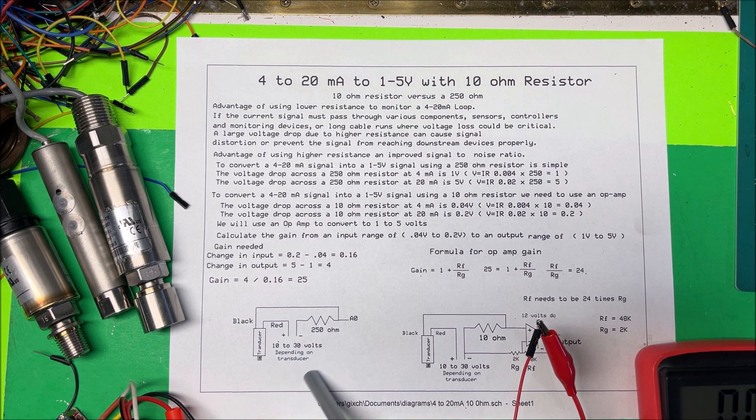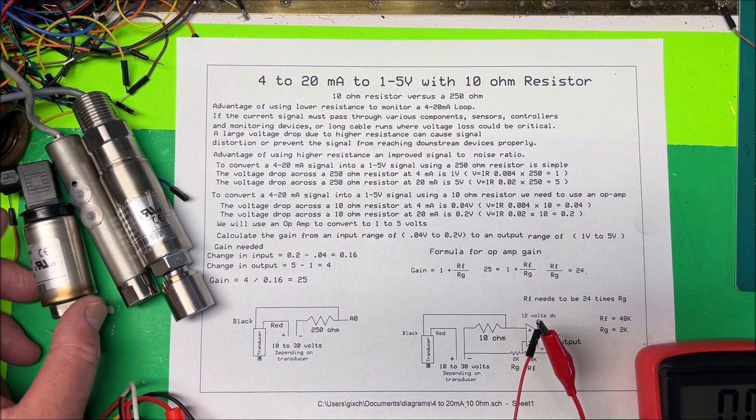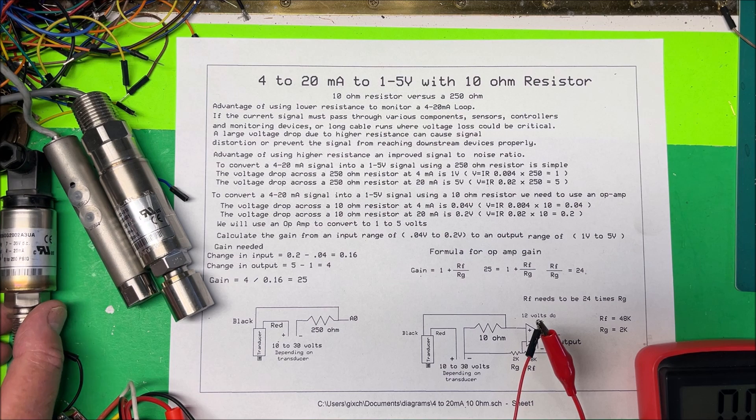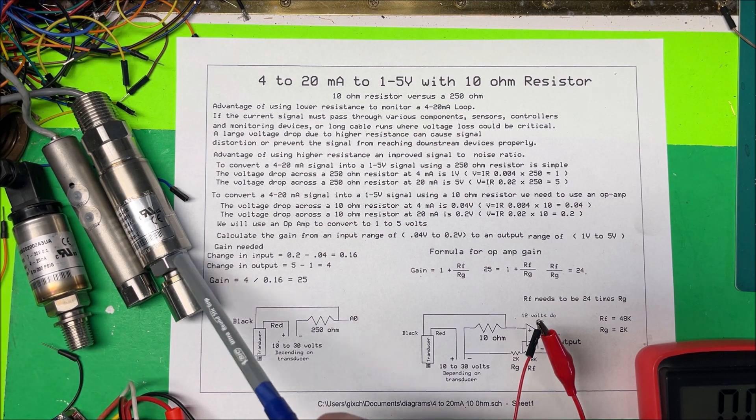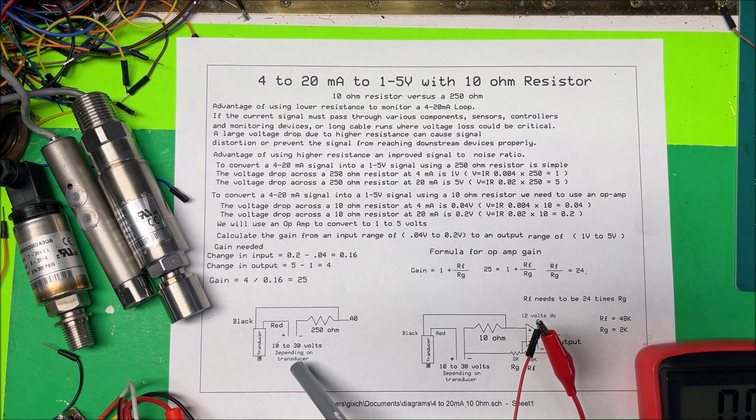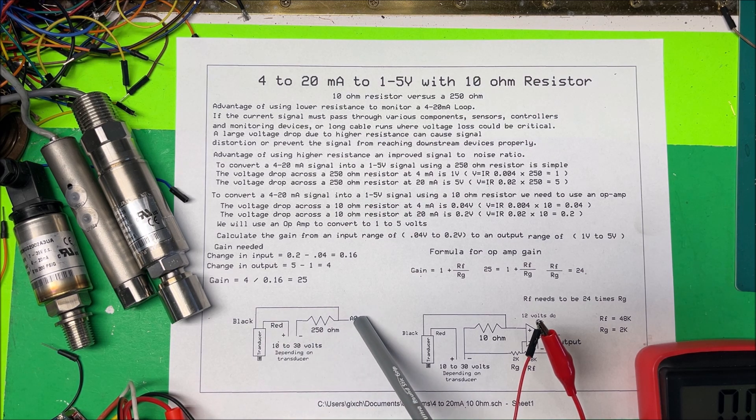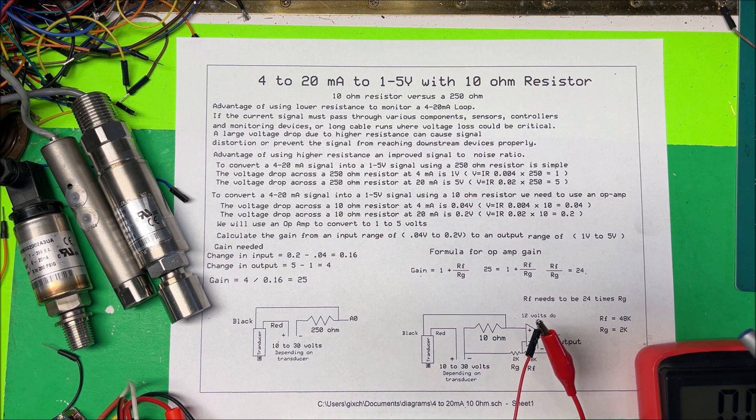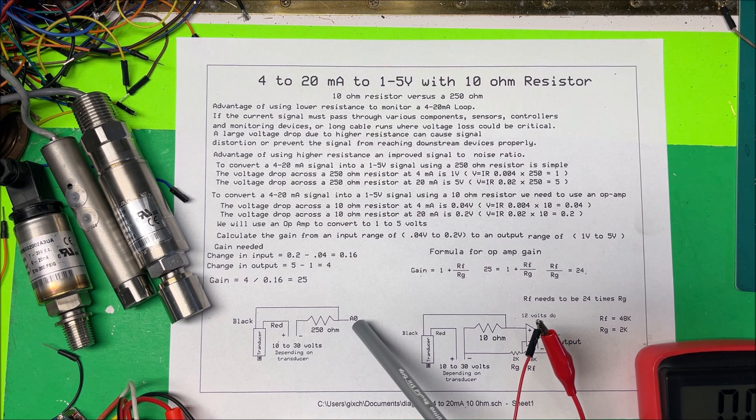This one's good from 7 to 35 volts, so depending on your transducer you can just put your voltage in there. Then coming out here it's going to go to the analog input on your controller, and you're going to put in 1 to 5 volts and it's going to correspond to how much pressure you have over here.